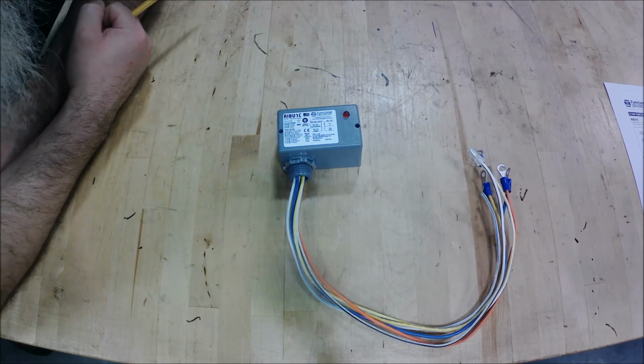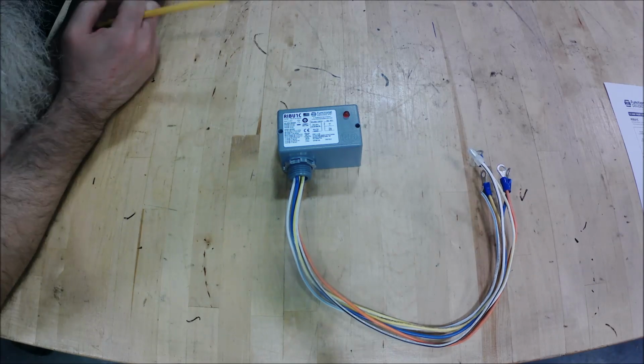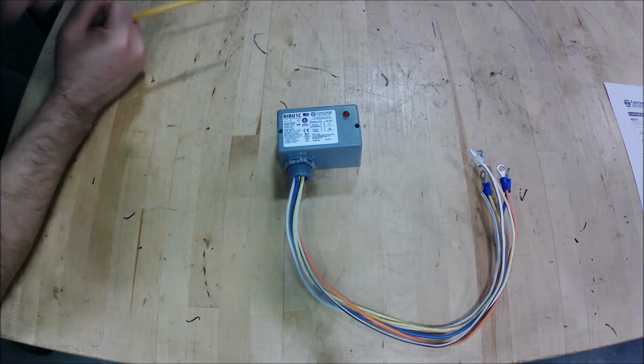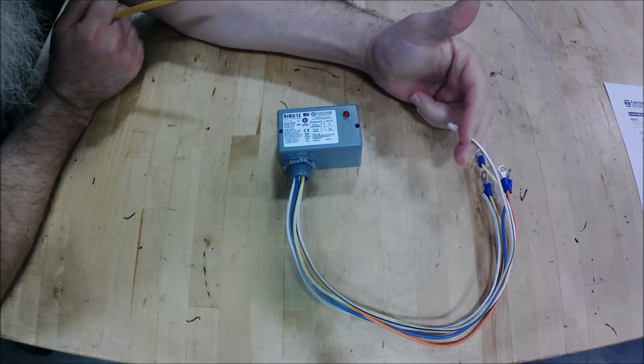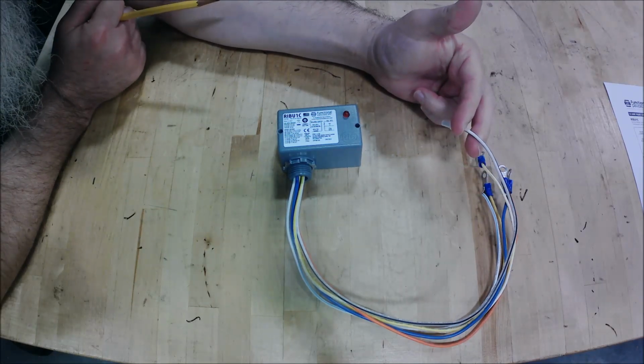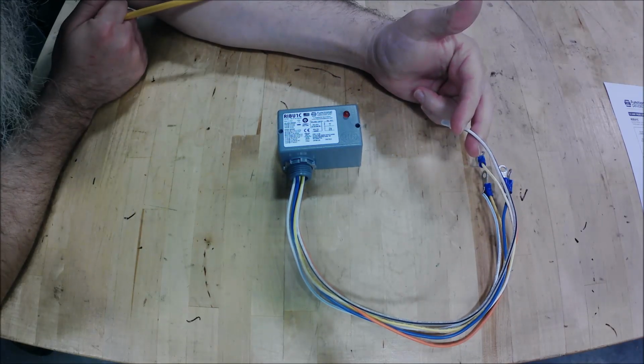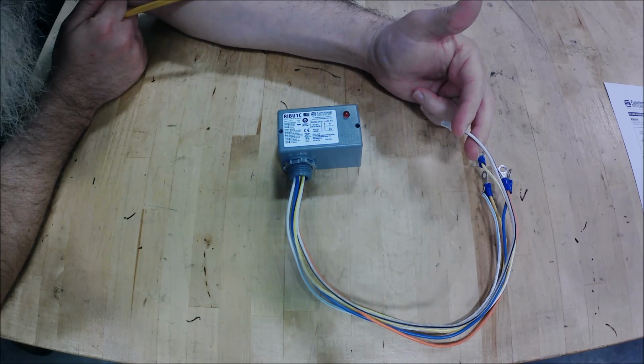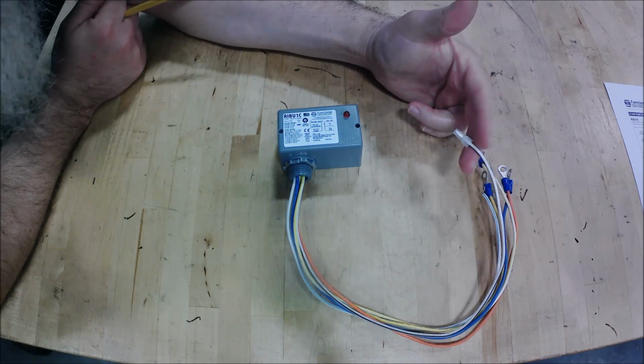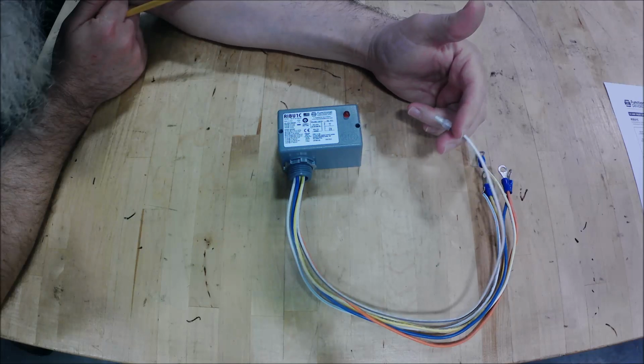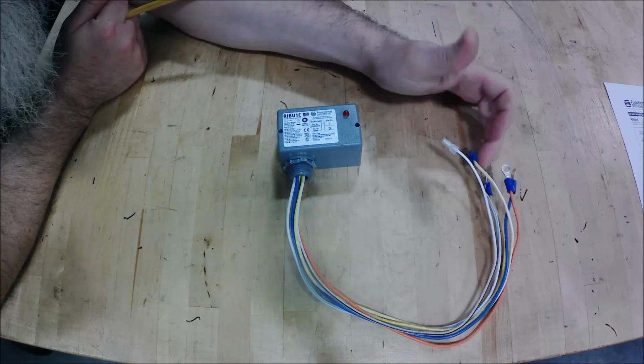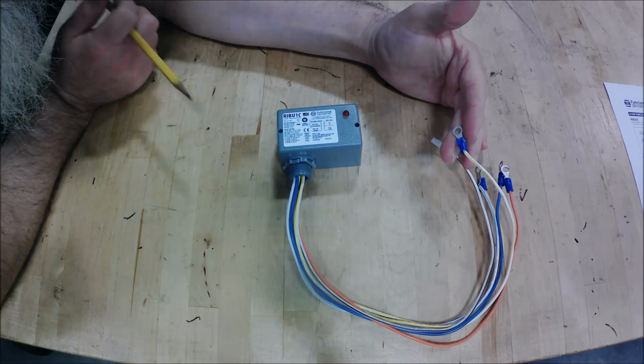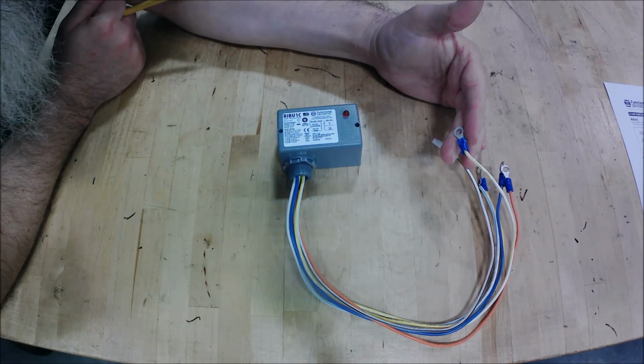So you just knock out one of the 1/2-inch knockouts, and you've got more than enough wire to go. What I'm going to do here is cap the 120 volt coil voltage connection wire that I have here. I'm just going to cap it and leave it there because you never know if you might want to use this relay somewhere else. And I'm going to use a ring on the end of all the wires that we are going to use today.